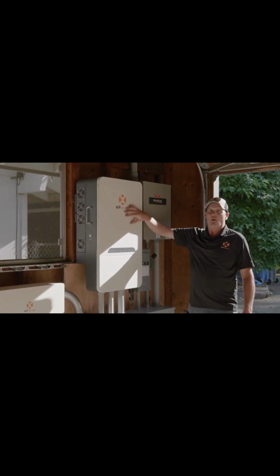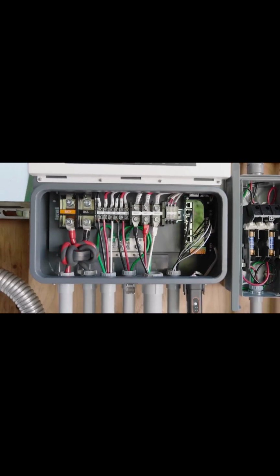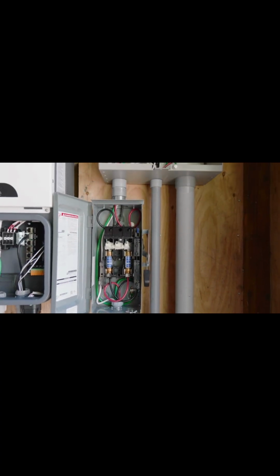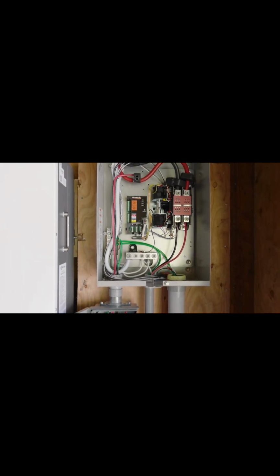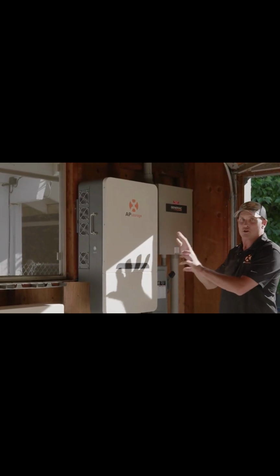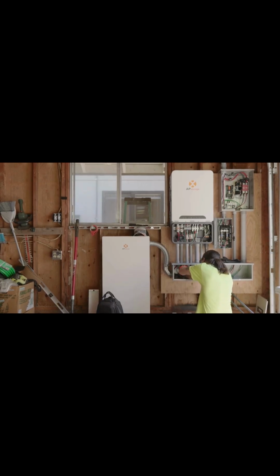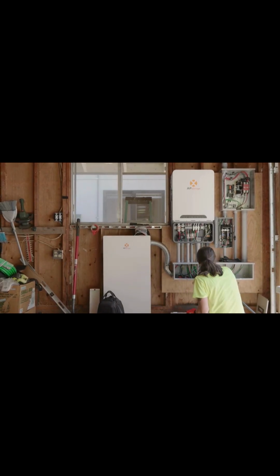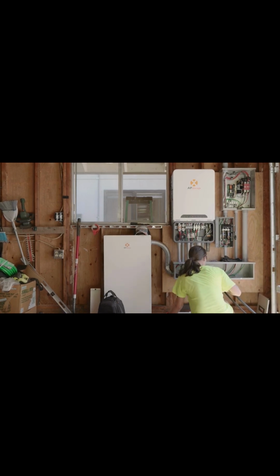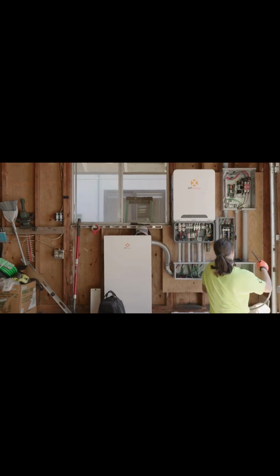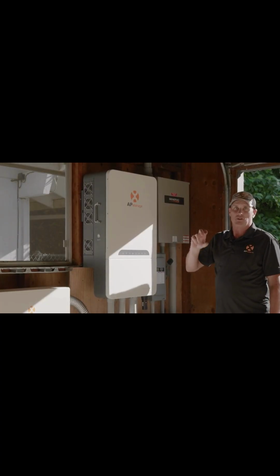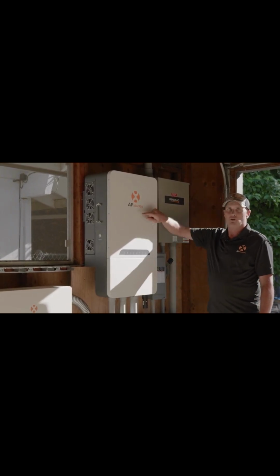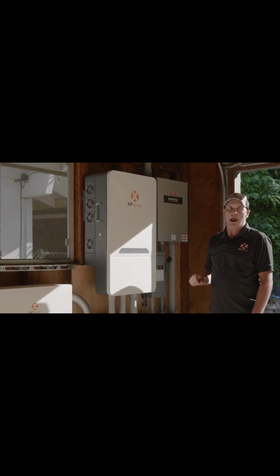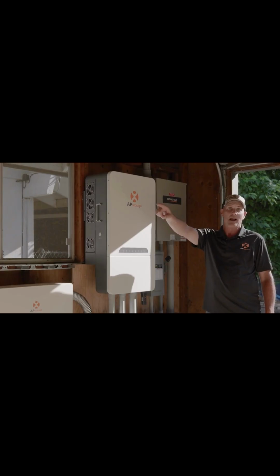So coming out of the 11.4 PCS for the utility connection comes through the PCS, lands inside this disconnect, and then from this disconnect, it goes to a line side tap at the top of this transfer switch right here. So that's the grid side of this system. The backup side of this system comes out of the PCS, lands on the normally open side of the transfer switch. And so when the grid goes down, the transfer switch is going to transfer power from the utility to the PCS, and the PCS is going to provide all that power straight to their 200 amp main electrical panel.